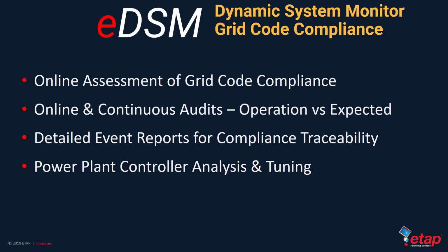So that's where the dynamic system monitoring recorder comes into the picture, that provides online assessment of grid code compliance. And it can do online and continuous operational audits based on operation versus expected response of the system. This includes detailed event reports for compliance traceability, and you can use this for power plant controller analysis and tuning.